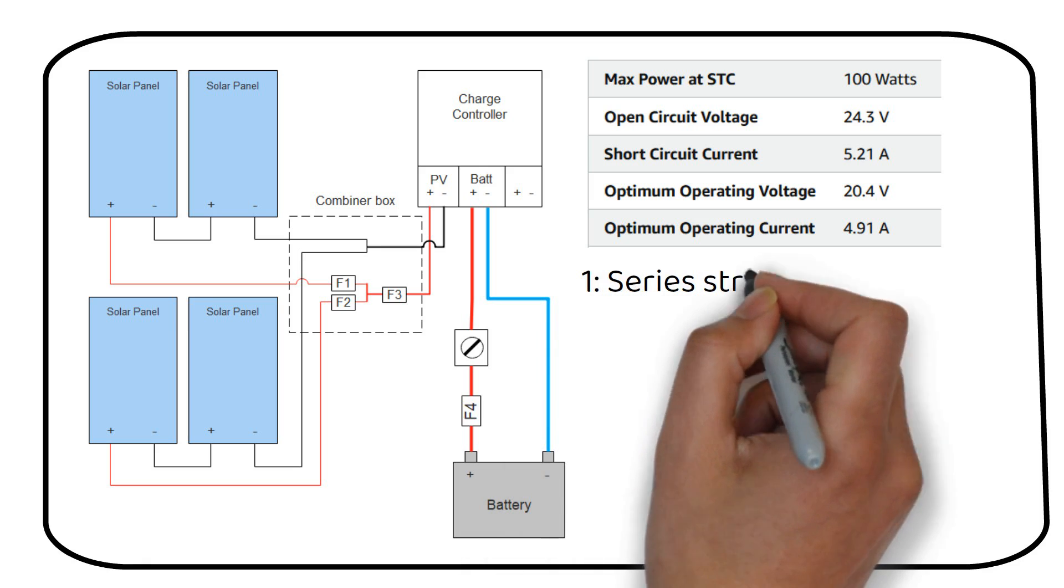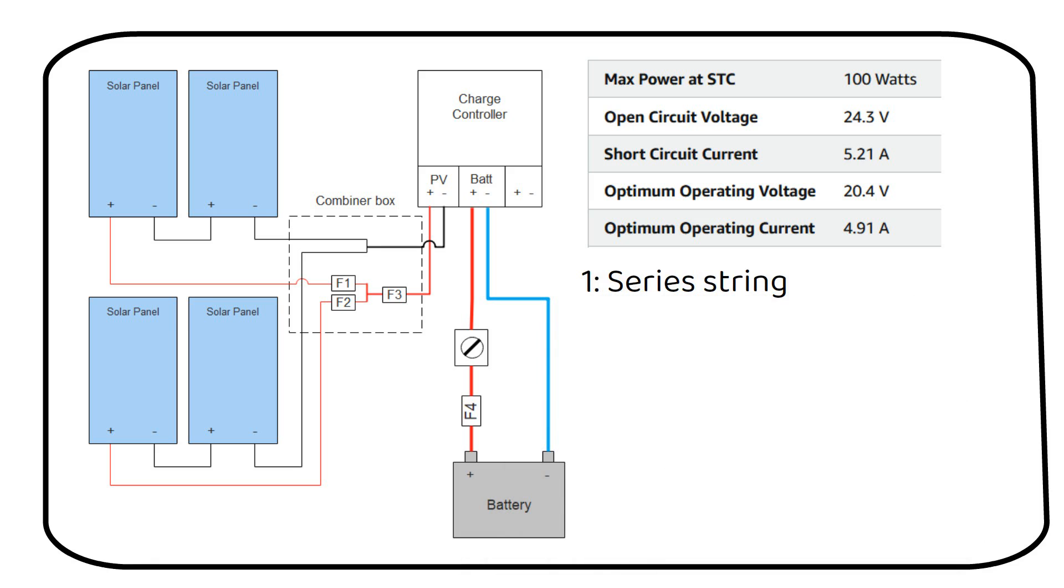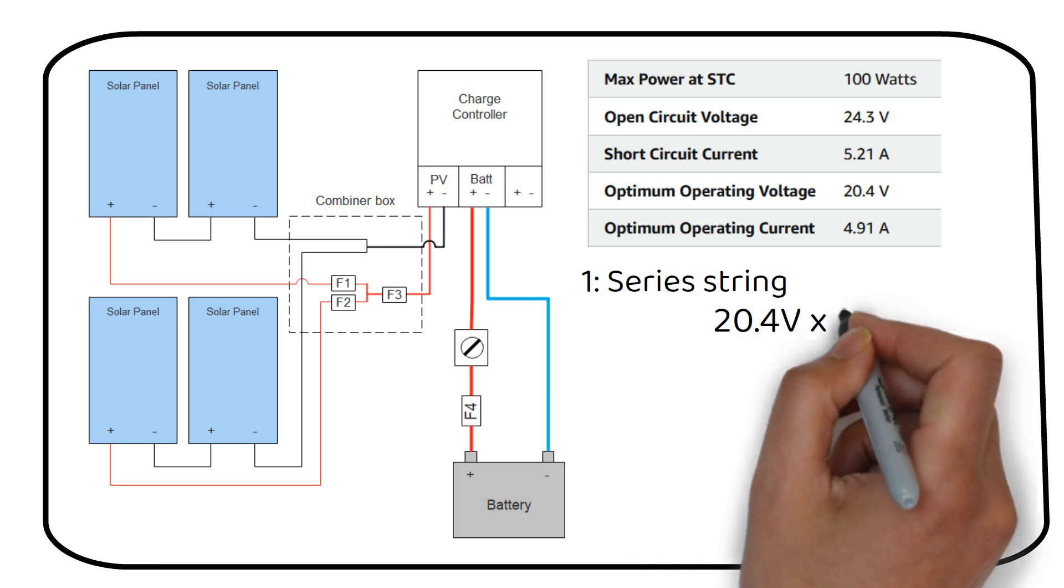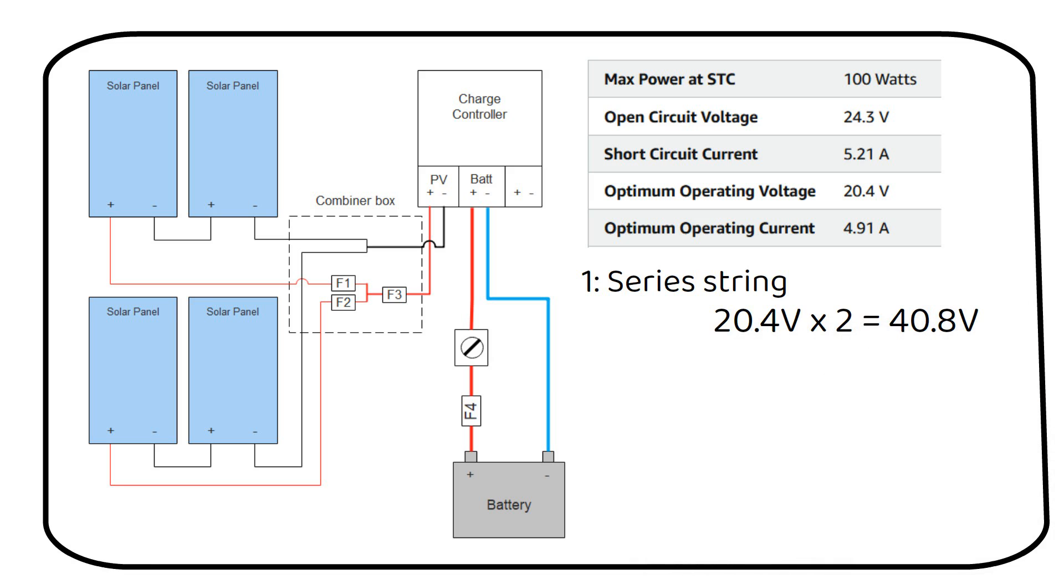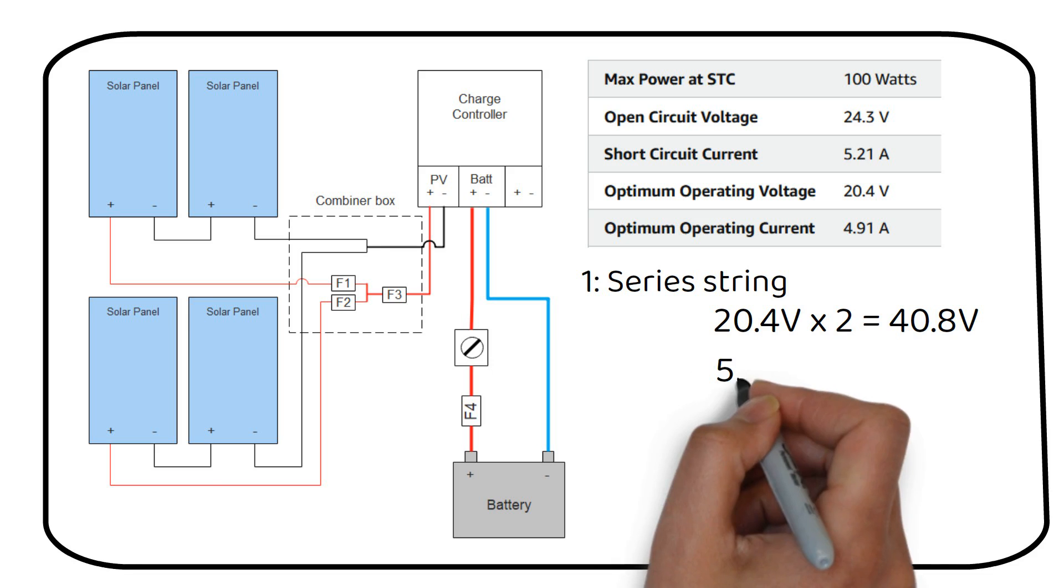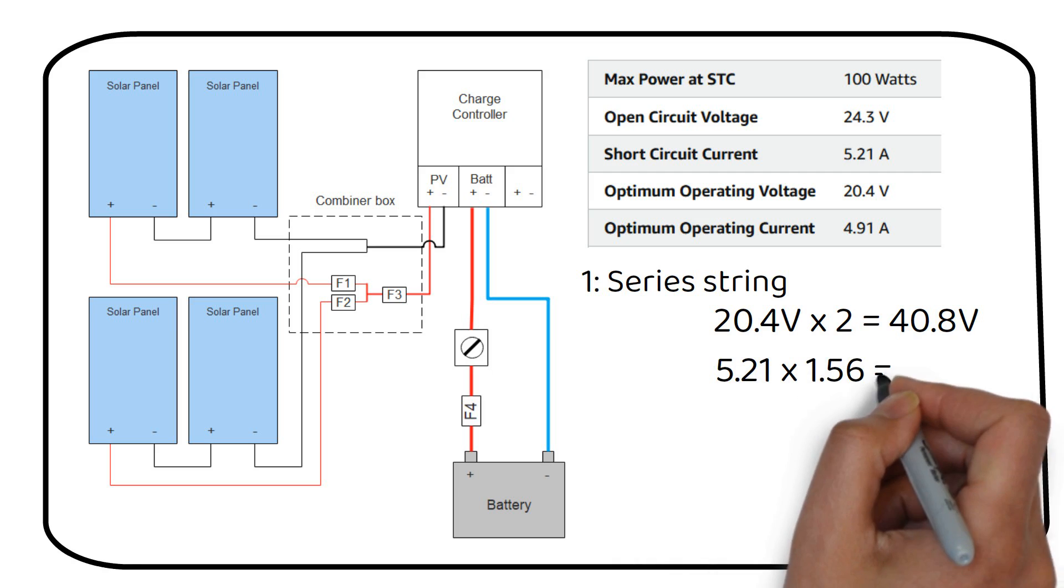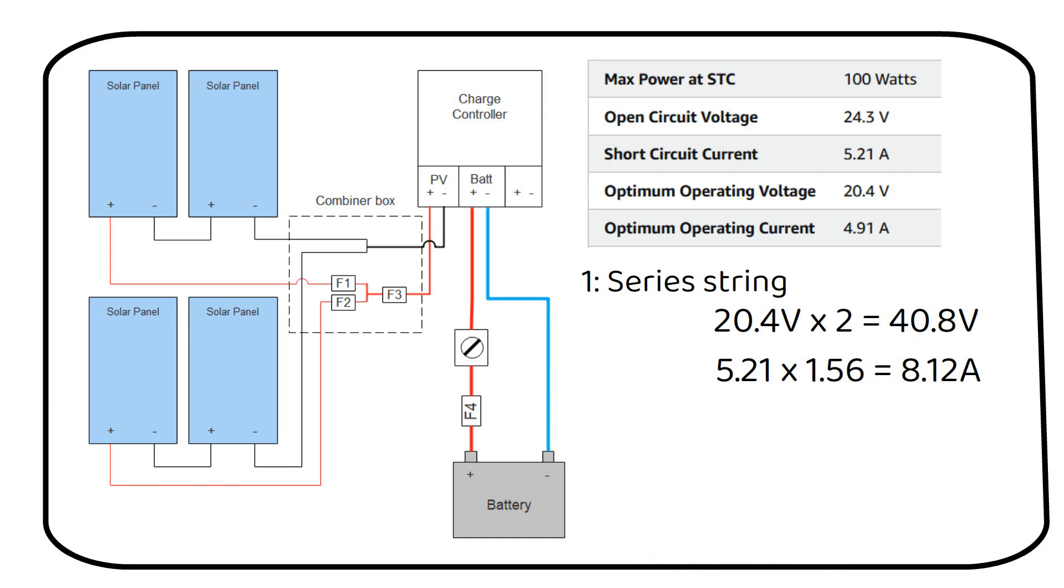Step 1: Calculating voltage and current for the series connection. For panels in series, voltages add up. So 2 panels with a VMP of 20.4V each gives us 40.8V in total. The current remains the same in series, but we apply our safety factor of 1.56. Thus, for panels with a short circuit current of 5.21 amps, the adjusted current is 8.12 amps.